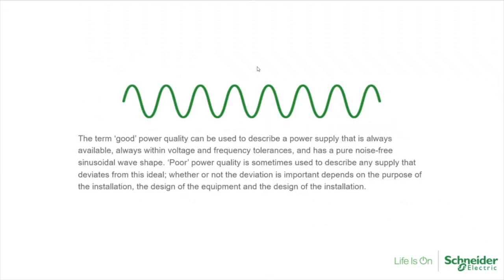The term good power quality can be used to describe a power supply that is always available, always within voltage and frequency tolerances, and has a pure, noise-free sinusoidal wave shape. Poor power quality is sometimes used to describe any supply that deviates from this ideal. Whether or not the deviation is important depends on the purpose of the installation, the design of the equipment, and the design of the installation. There are a lot of power quality corrective devices, active and passive equipment.